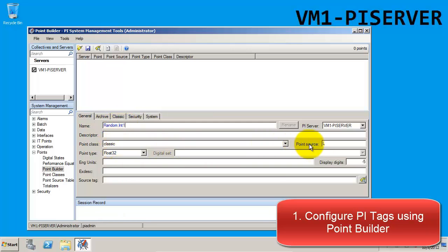Because this is an OPC tag, we want to make sure that the point source matches what's in the interface, which is OPC. And since this is an integer tag, we'll go ahead and change the point type to Int.